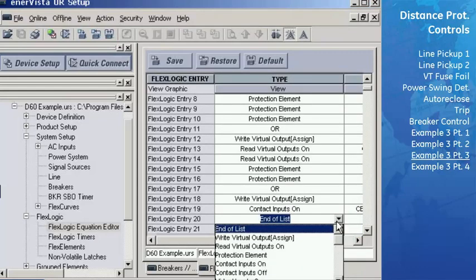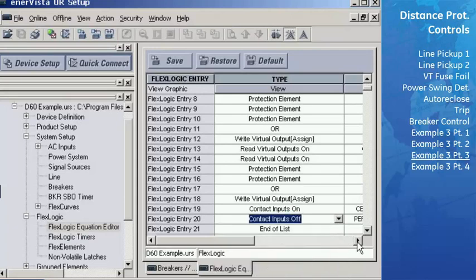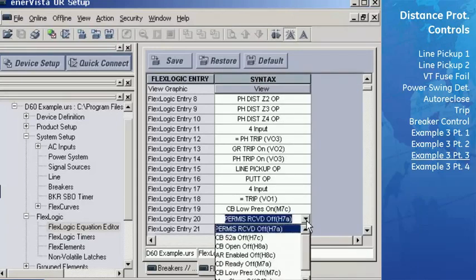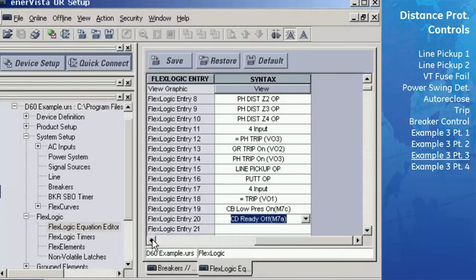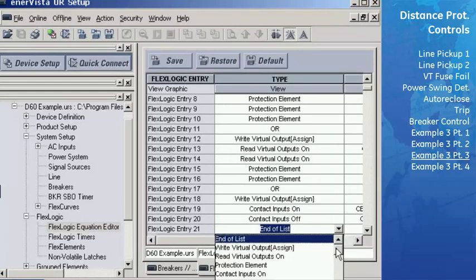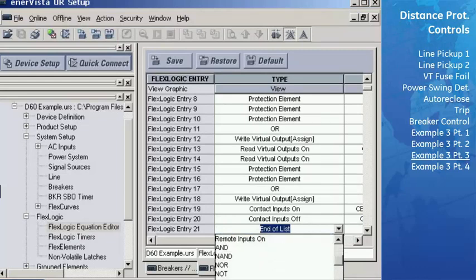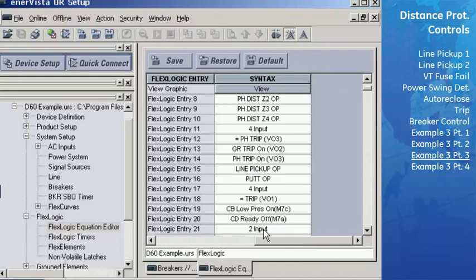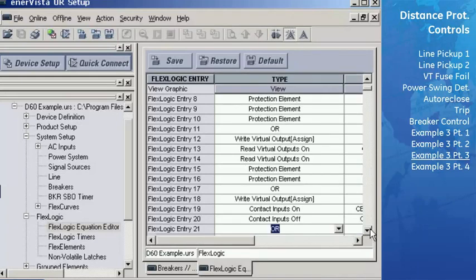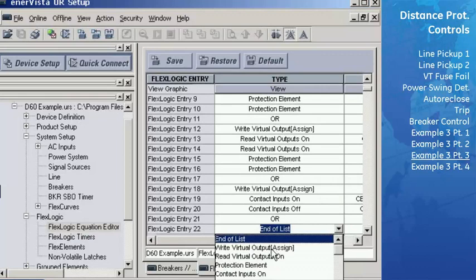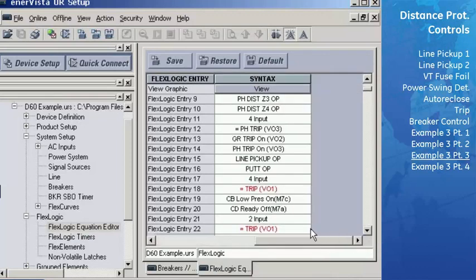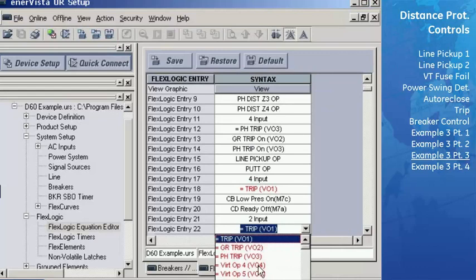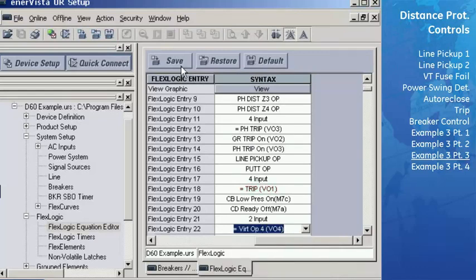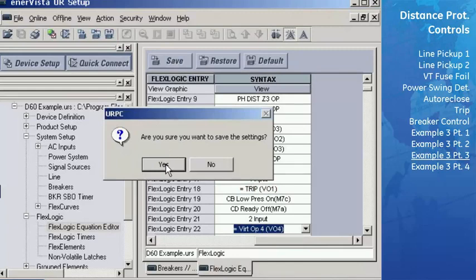In the next line, select Contact Inputs Off in the type field and select CB Ready Off or M7A in the syntax field. Then OR these two signals together, and write them to virtual output 4. Save these settings and close the window.